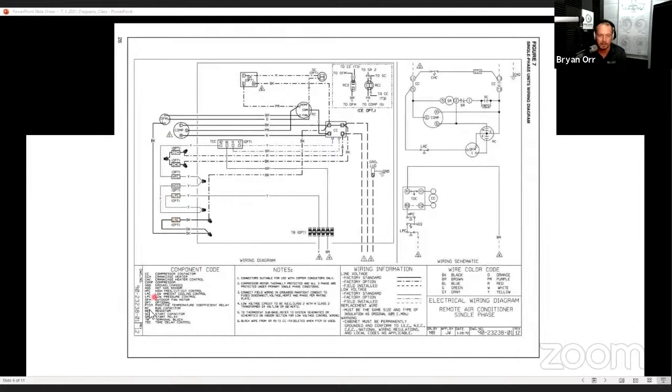All right. Any questions? So you're going to notice that in terms of symbols, we got a lot more symbols on this side. So we got some information over here that we don't get over here, right? We don't have all this cool information about the switches and what causes them to open and close on this side. But on this side, we don't have colors of wires. We don't know exactly where they're connected. So you're going to have to kind of jump back and forth. I prefer to start over here on the ladder side just to get a sense of the circuits. And then once I'm tracing an individual circuit, so I've already kind of got a sense of where I want to go, then I move over here to my point-to-point or connection diagram, or in this case, they're just calling it a wiring diagram.